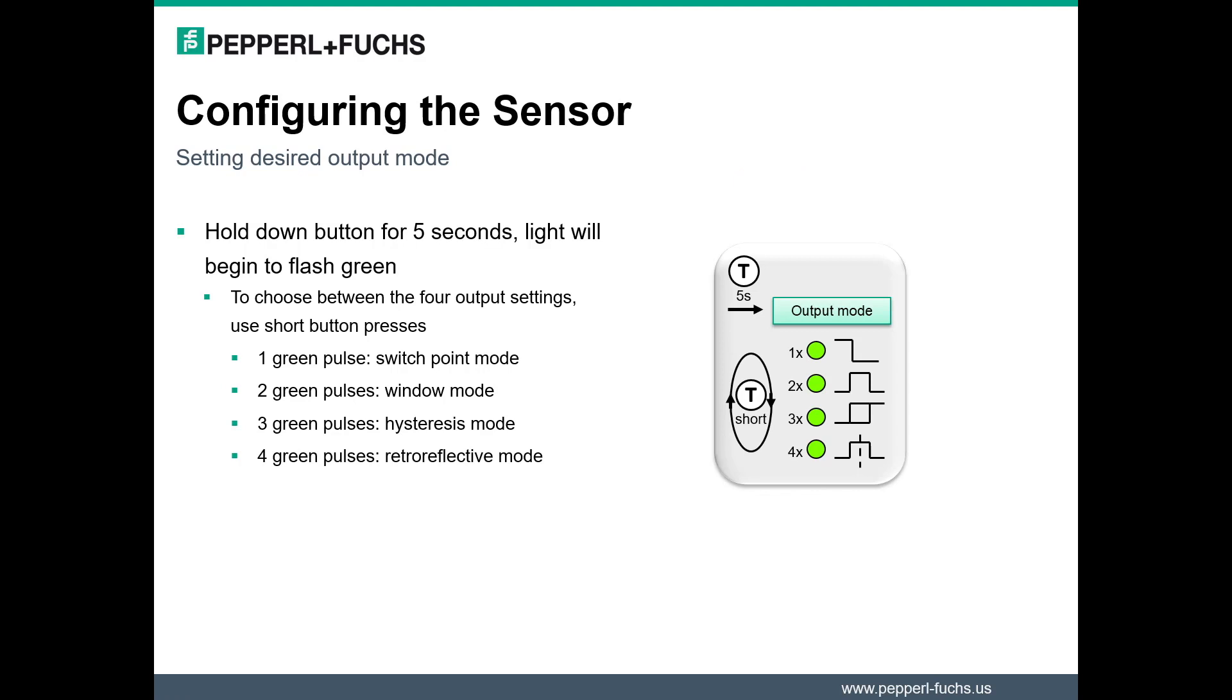To configure the sensor for its output mode, we will first hold down the push button for 5 seconds until you see the light begin to flash green. Then, to cycle between the four output settings we discussed earlier, use short button presses. One pulse indicates switch point, two pulses indicates window, three for hysteresis, and four for retroreflective.